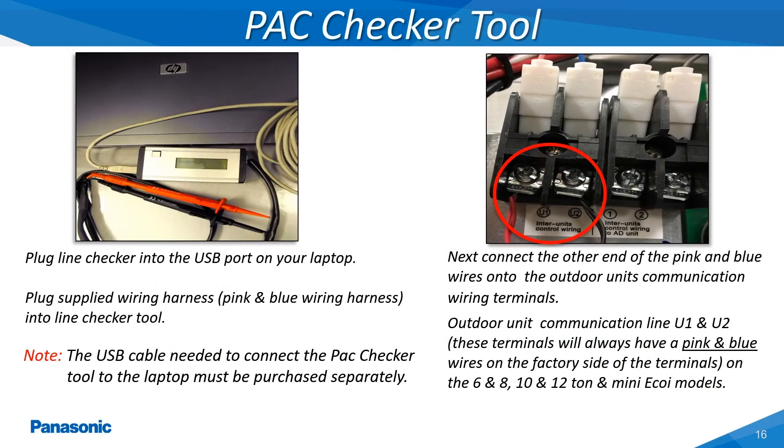The PAC Checker tool can be installed at any one of three points within the Panasonic VRF system: the indoor unit, outdoor unit, or central control device at the U1 and U2 low voltage communications terminals. The outdoor unit's refrigerant circuit number must be known to select the proper refrigerant circuit to be monitored, especially on installations where multiple systems are installed and the low voltage wiring is linked together through the U1 and U2 low voltage terminals.